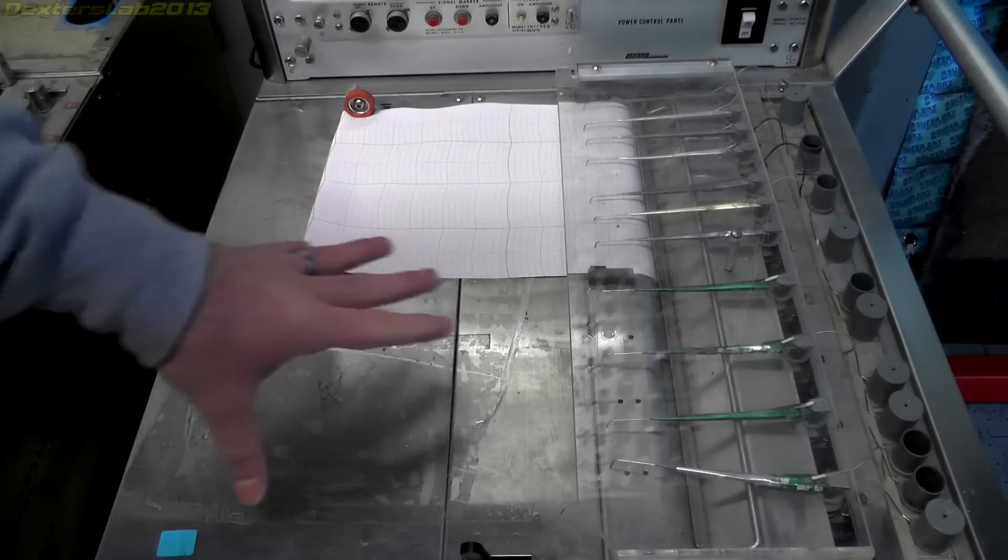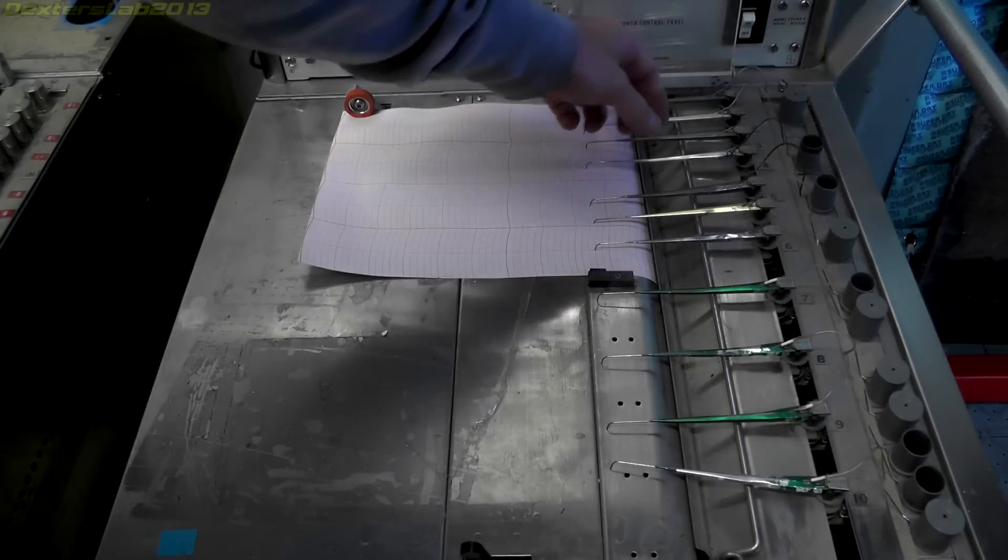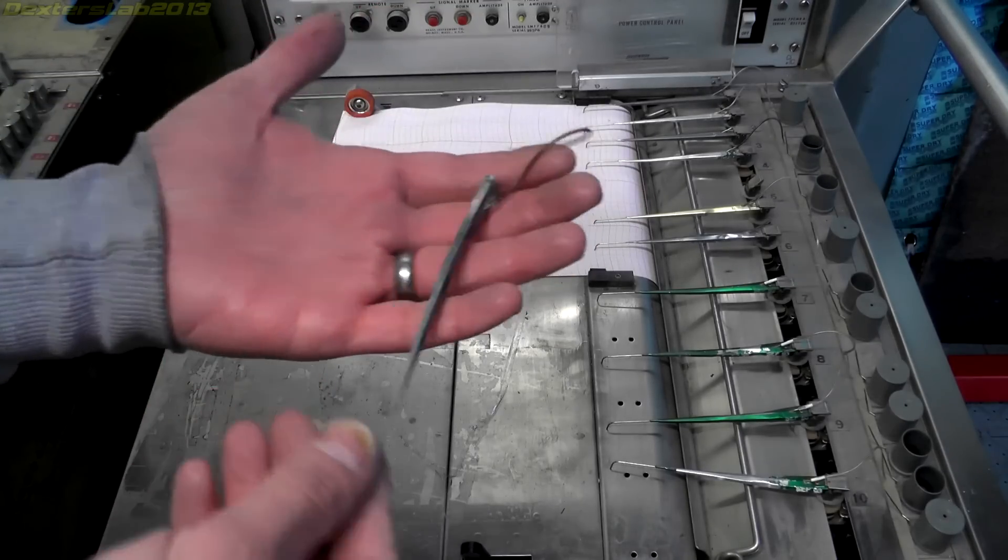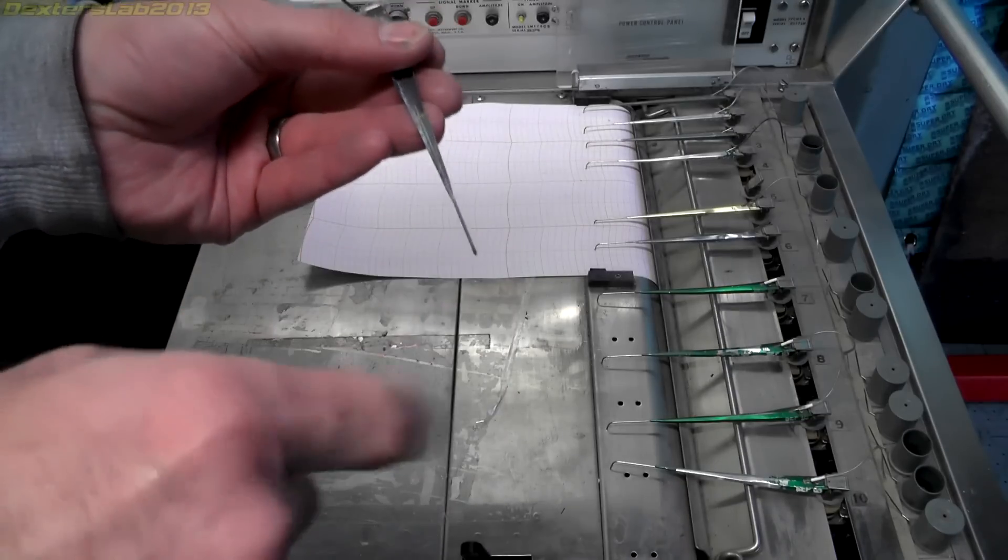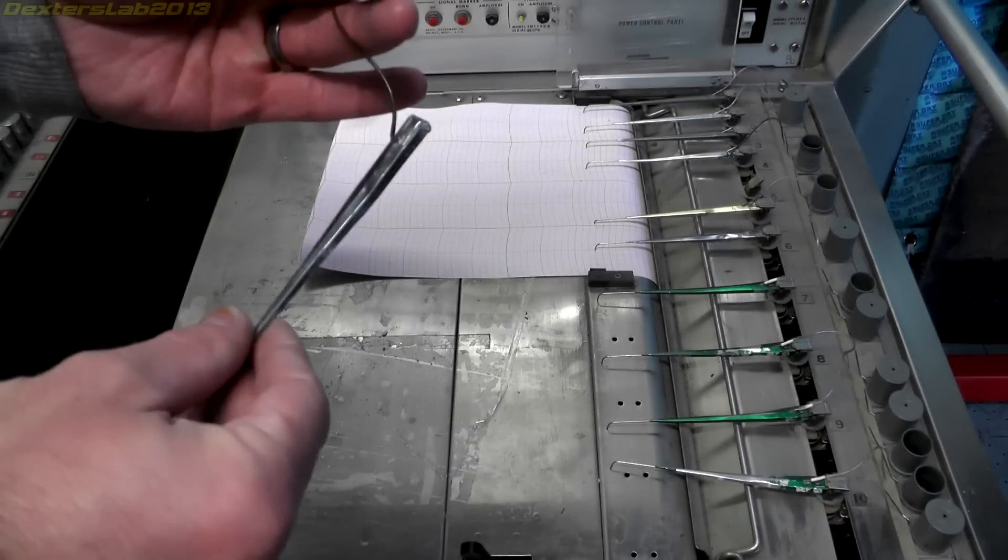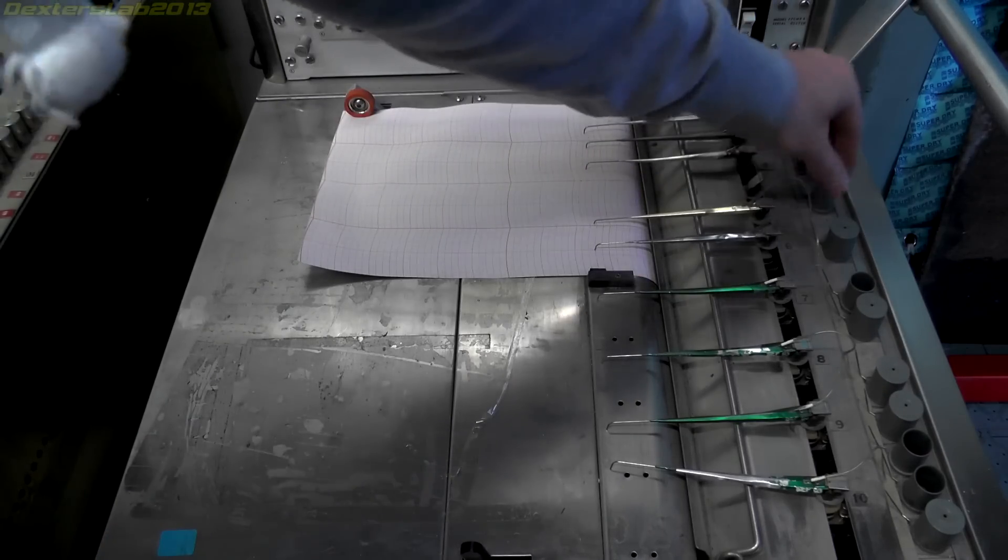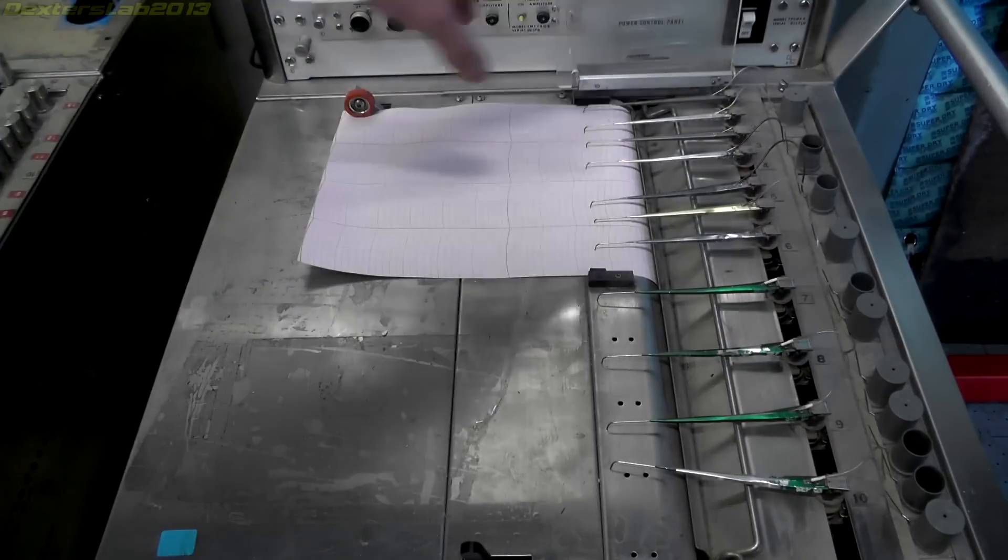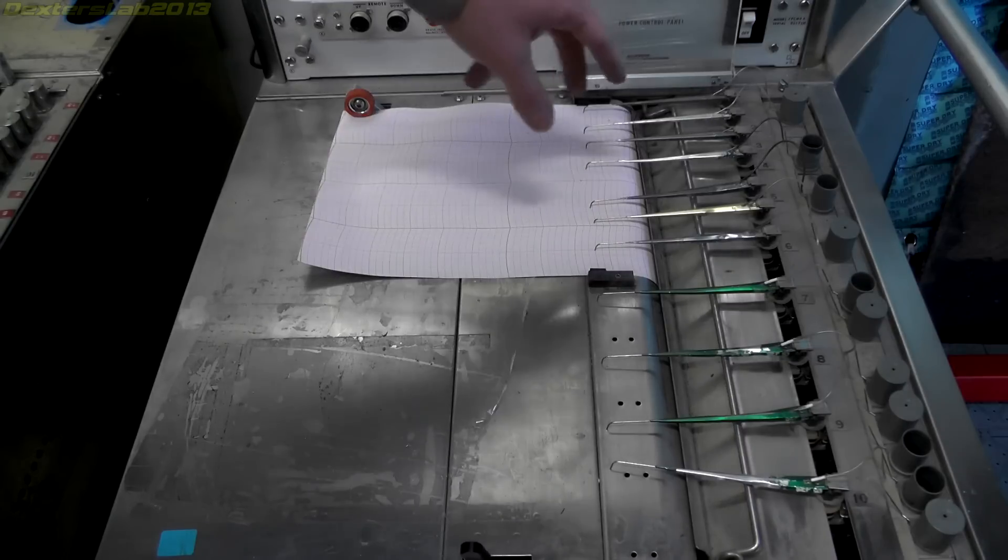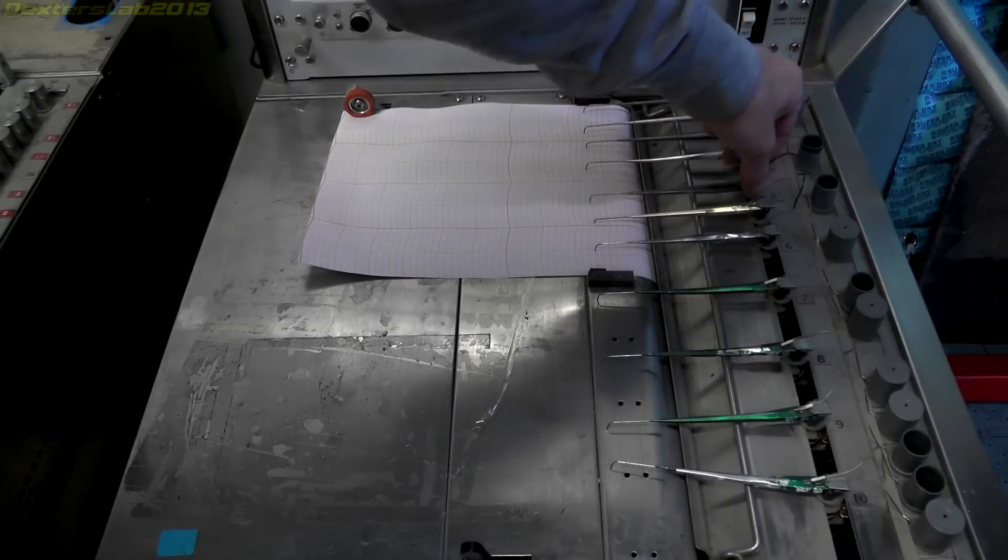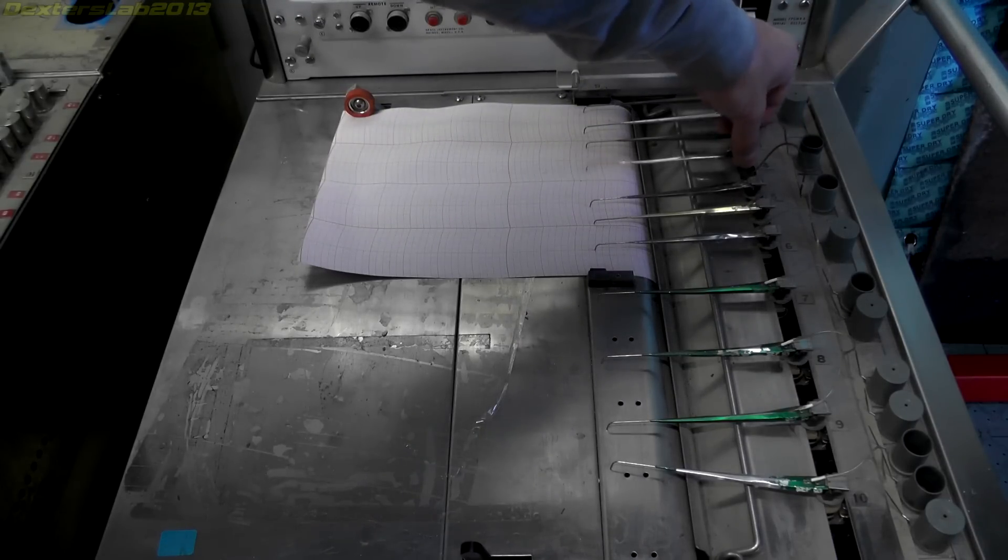So if we have a quick look at the chart recorder. We've got this plastic cover here. These are the actual pens. These are removable. They're just a very thin flimsy piece of aluminium, very light, with a small capillary pen which actually draws on the paper. With a small tube which connects to the inkwell which is just here. These are obviously all dried up and there's nothing left in those. So each of the pens has a voice coil and each one of those is connected to the DC driver amplifier which I showed you earlier. So these would move backwards and forwards on the paper to actually create the chart.